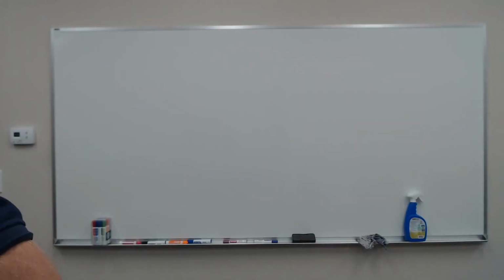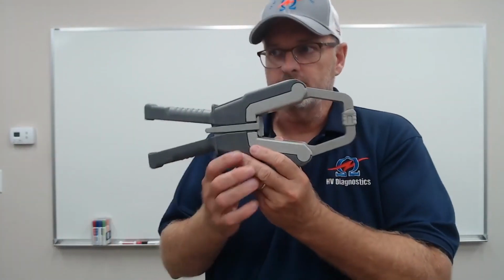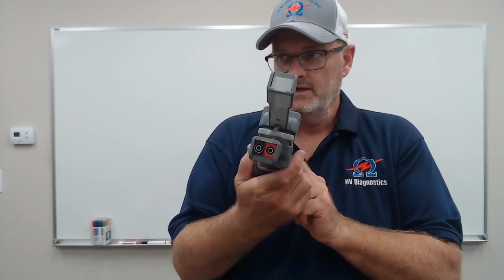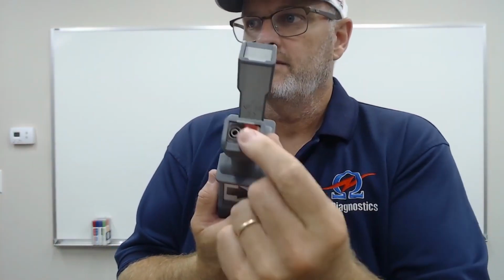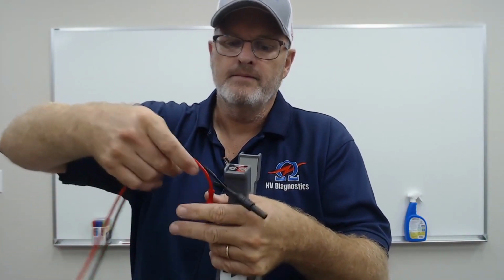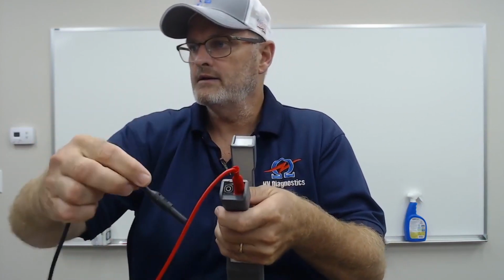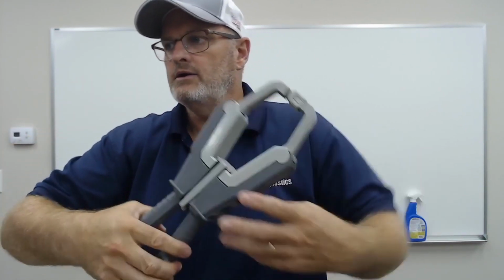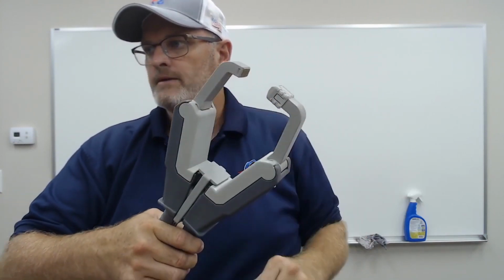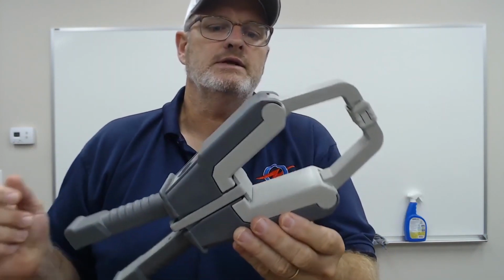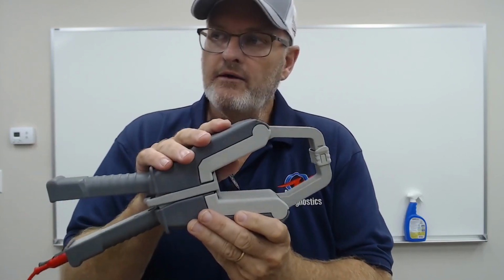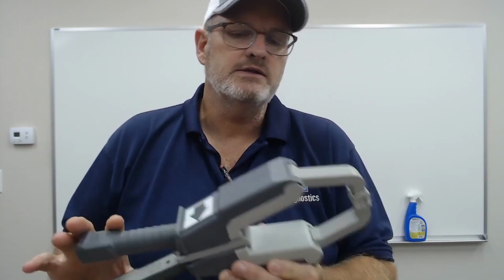Okay, apart from hooking up directly like we've just shown over there, we also have the ability, if you go down to look at the induced method, where we can induce onto a live cable. How we do that, these live CT clamps have these ports over here, which are banana female ports. And what you do, you take that same cable that you had before, and you connect red to red and black to black. And now you connect that through the cable, and you then have the ability to induce the signal into the cable.